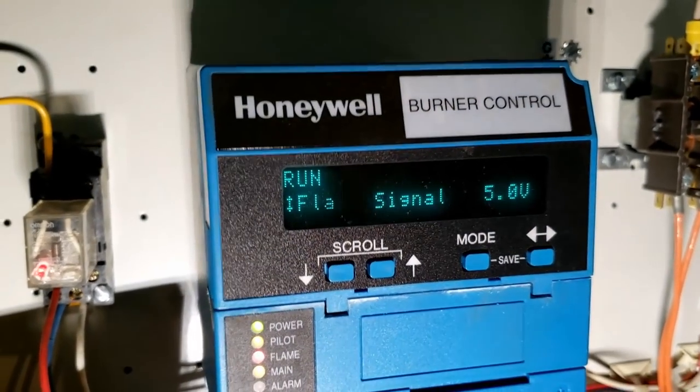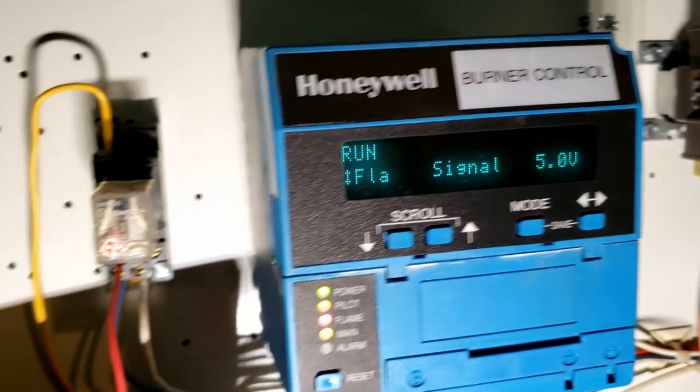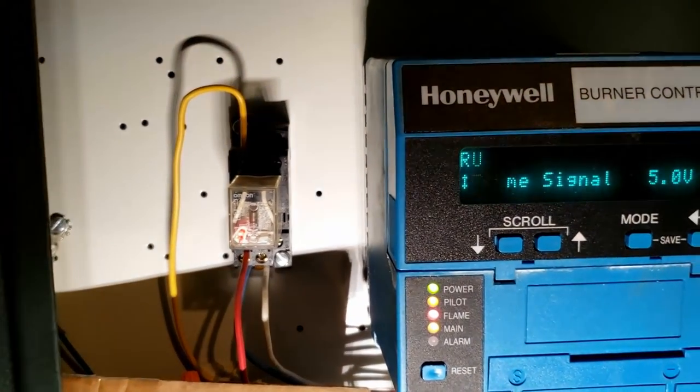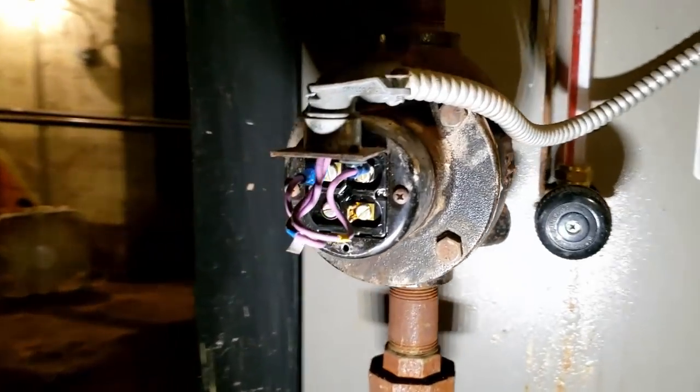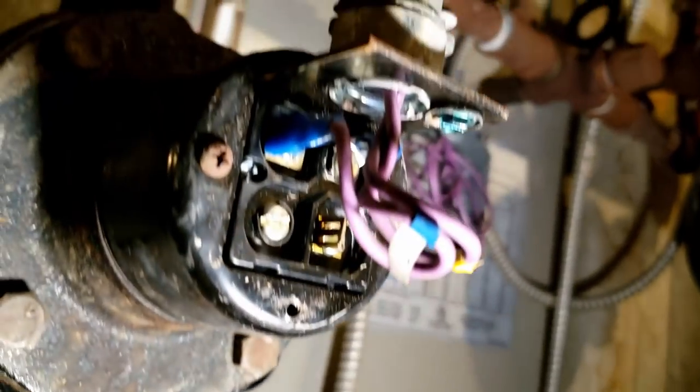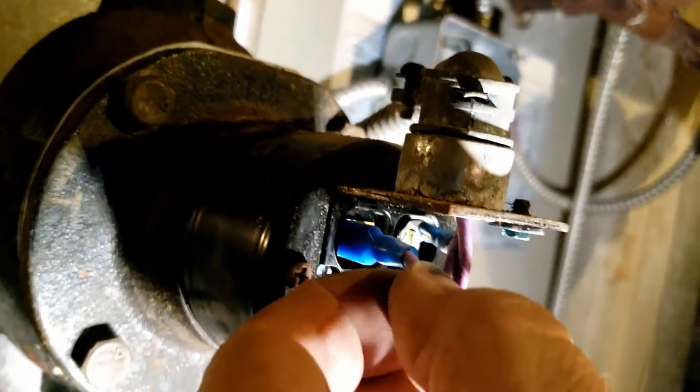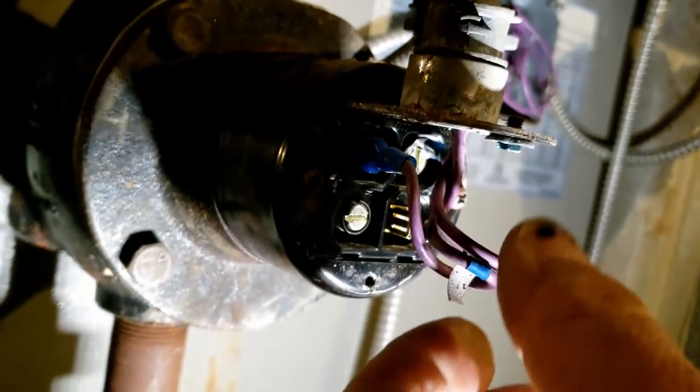Flame signal's at five volts, which is good. There's the end contact, so the low water cutout - everything on it looked pretty good, it's tight.